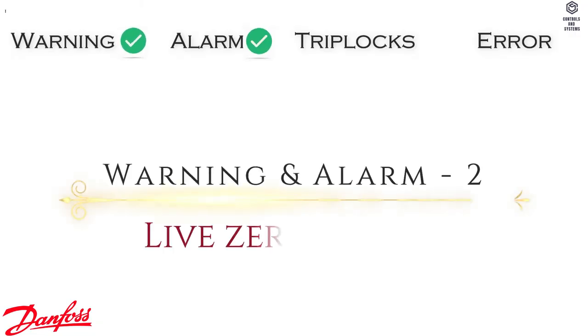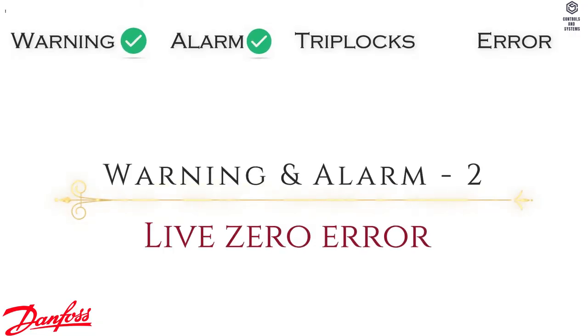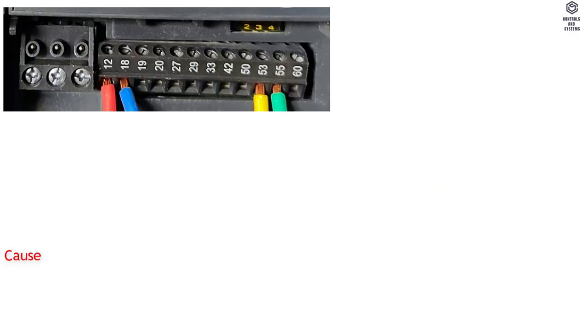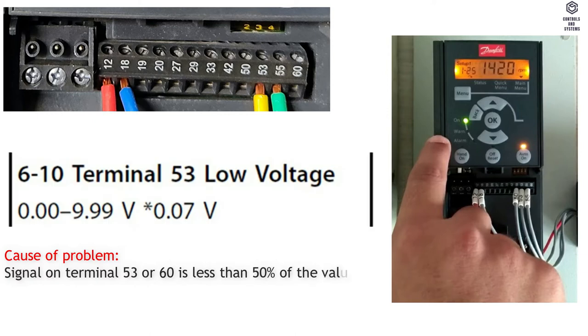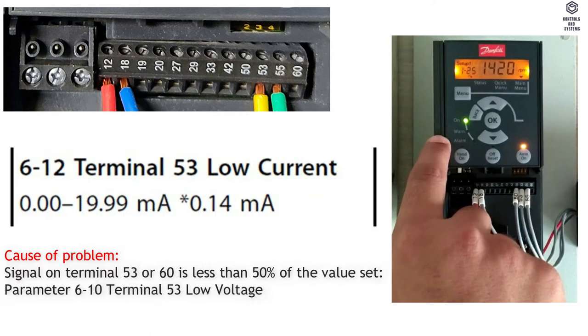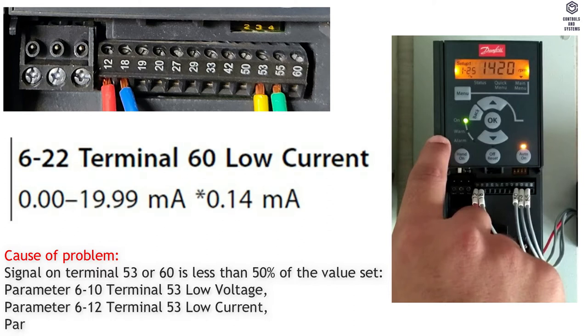Warning and Alarm 2: Live Zero Error. Cause of Problem — signal on Terminal 53 or 60 is less than 50% of the value set. Parameter 6-10, Terminal 53 Low Voltage. Parameter 612, Terminal 53 Low Current. Parameter 6-22, Terminal 60 Low Current.